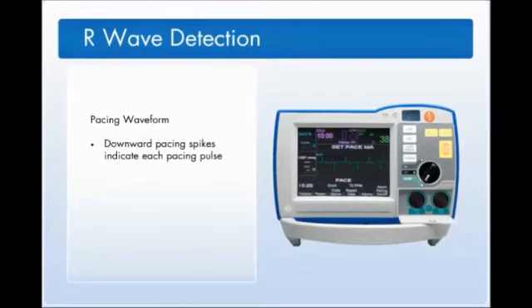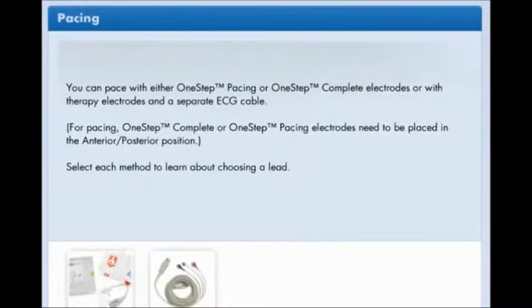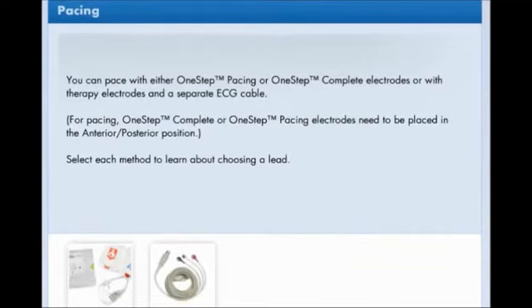The downward pacing spikes indicate each pacing pulse, and the heart-shaped symbol flashes each time the defibrillator senses an R wave. The lead vector will change depending upon which electrodes you are using for pacing. When the one-step pacing and one-step complete electrodes are used, the R series will display and print the lead labels as P1, P2, and P3. If standard leads are required, you can apply a separate cable with conventional ECG electrodes to view standard leads 1, 2, and 3. Select each method to learn about choosing a lead.